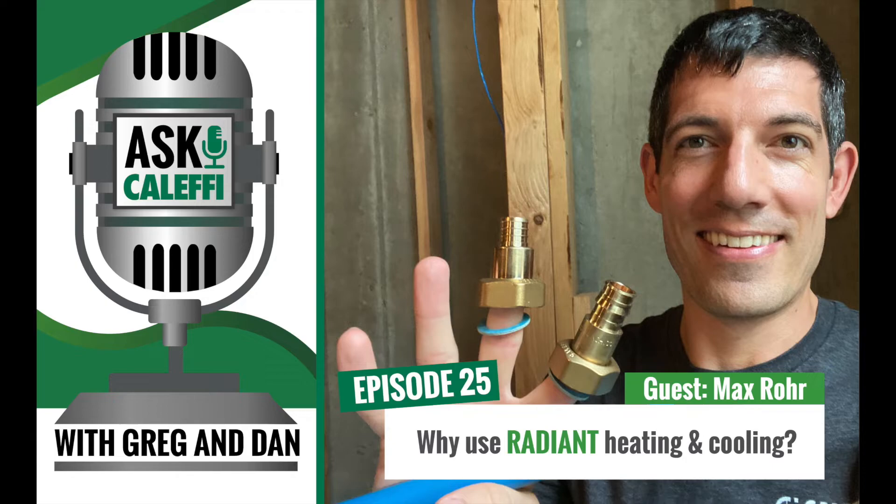One of my first calls when I got here was a contractor who had non-O2 barrier PEX and had no idea. He called pretty upset that the system - put in maybe six months beforehand - was pinhole leaking. One thing leads to another and you find out it's old PEX that's non-O2 barrier. The only thing you can recommend at that point is to put in a heat exchanger to separate that part of the system away from the primary. That's the best recommendation - separate it completely and you protect the rest of your new expensive components.